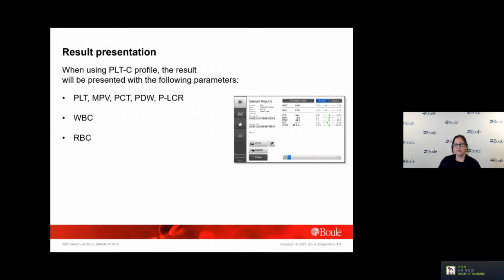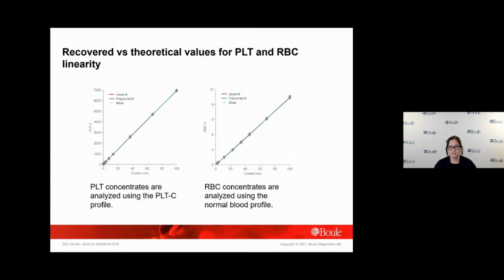When using PLTC profile, the results will be presented with fewer parameters. The platelet linearity in the PLTC profile ranges up to 5,000 billion cells per liter, as compared with up to 1,800 billion cells per liter in the normal blood profile. Red cell concentrates are analyzed in a normal blood profile with a linearity range of up to 7 trillion cells per liter.